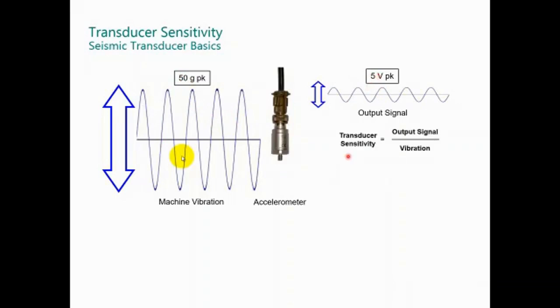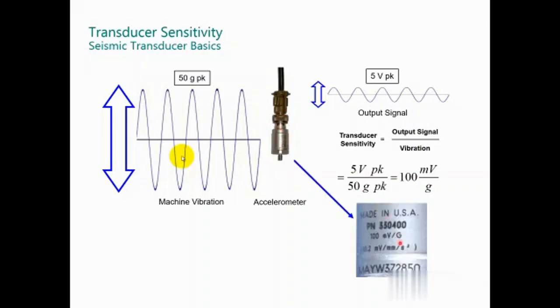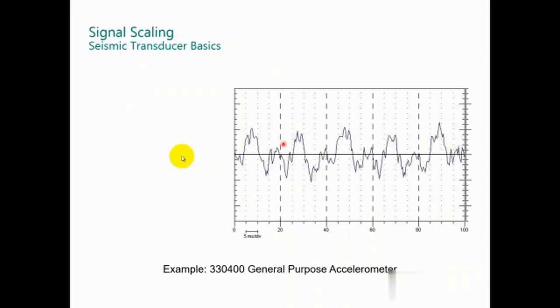Now, the transducer sensitivity is the output signal divided by the vibration. In this case, it's 5 volts peak to peak divided by 50 g's or 100 millivolts per g. This is the scale factor for this seismometer. This is written in the label for the transducer.